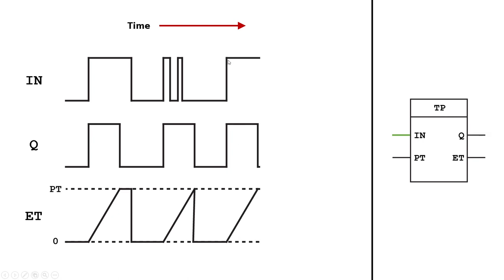Let me illustrate how the pulse timer works in code. I dropped in a pulse timer function block called Timer 1, gave it one input, and set a preset time of 7 seconds — that's going to be the length of our pulse. I also added a variable of time data type so we can see how long the pulse has been activated for. That's our elapsed time.